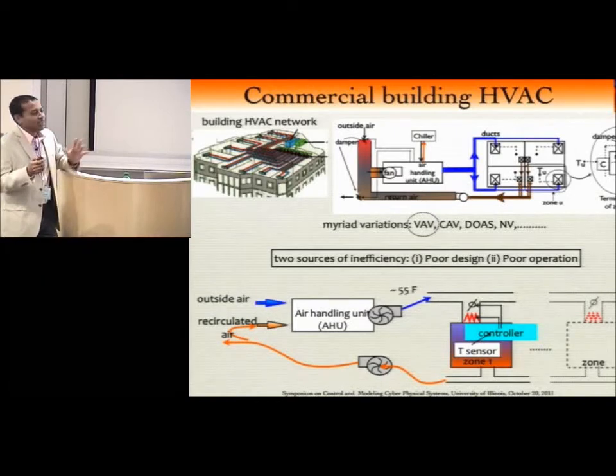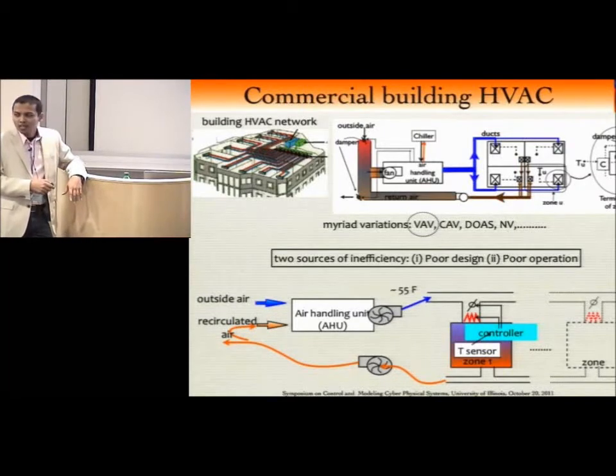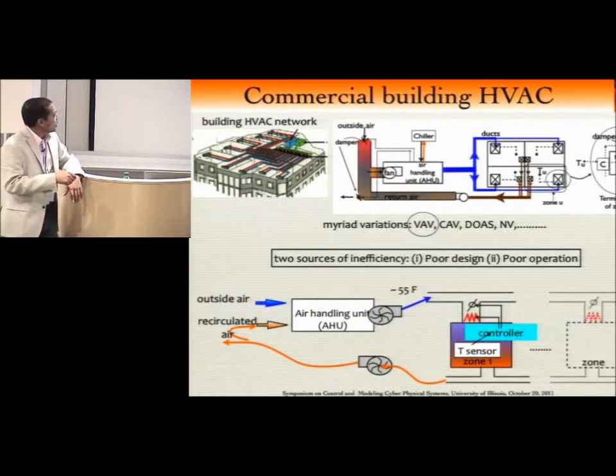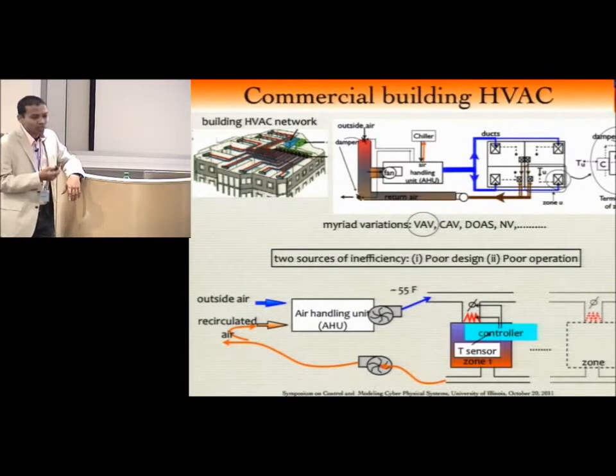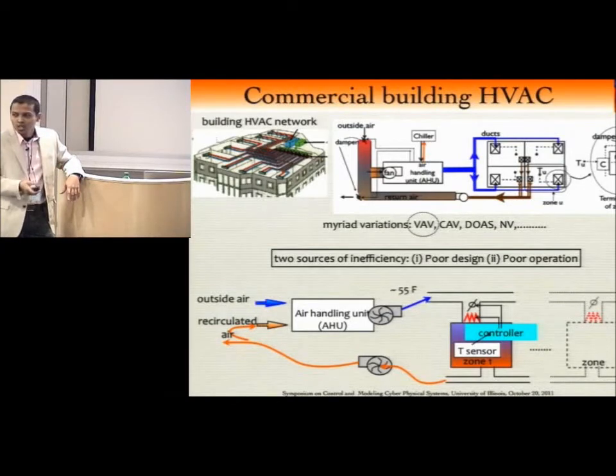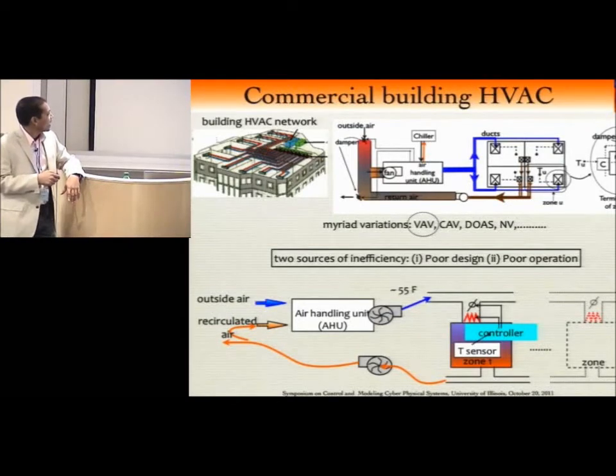So buildings have these things called air handling units, like big air conditioners basically. They are installed either on the roof of the building or in some floor between the top floor and the roof, which building operators fondly call the penthouse. So what happens is that there's the outside air that comes in, and some of the return air, some of the air that is exhausted out of the building is not completely let go. It's recirculated. That is to improve energy efficiency actually, because there's a lot of energy that is consumed in conditioning the air. You don't want to lose all of that. So all that is brought back into these air handling units.